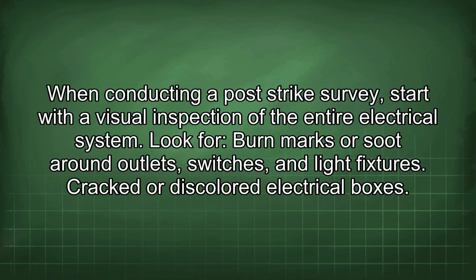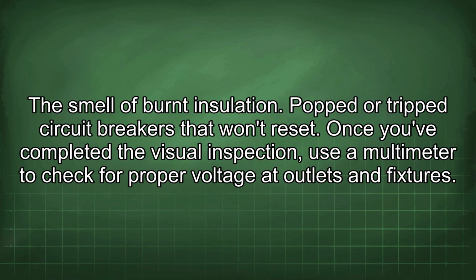When conducting a post-strike survey, start with a visual inspection of the entire electrical system. Look for burn marks or soot around outlets, switches, and light fixtures. Cracked or discolored electrical boxes. The smell of burnt insulation. Popped or tripped circuit breakers that won't reset.